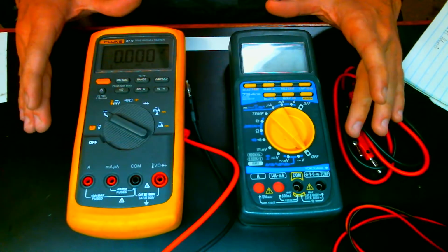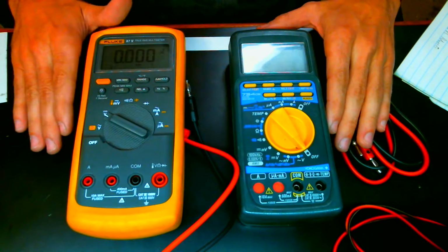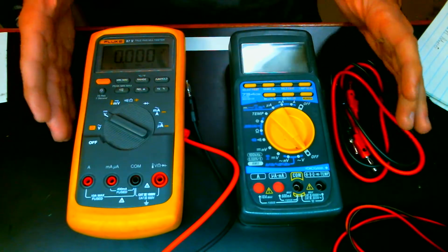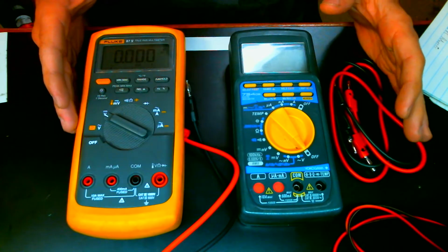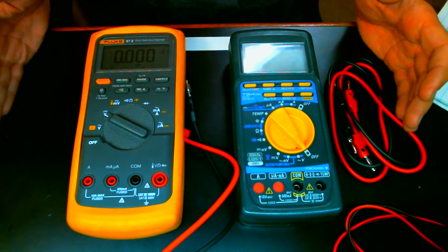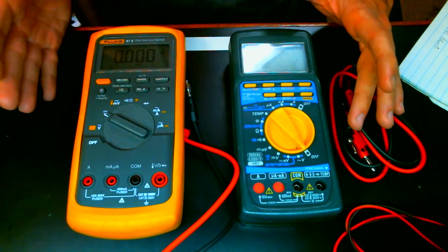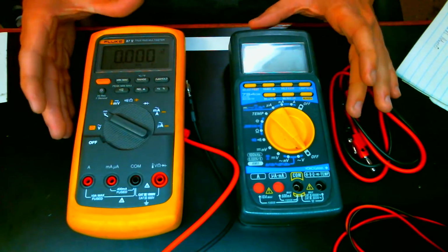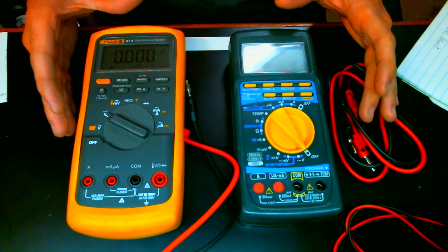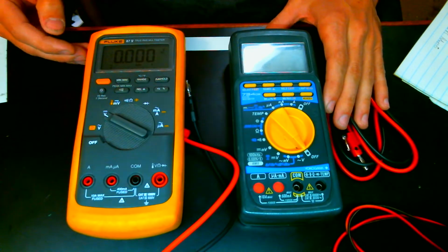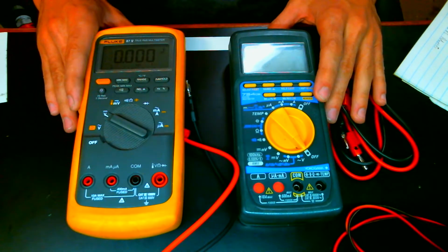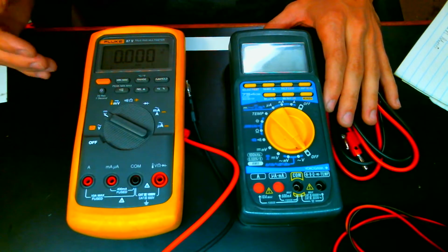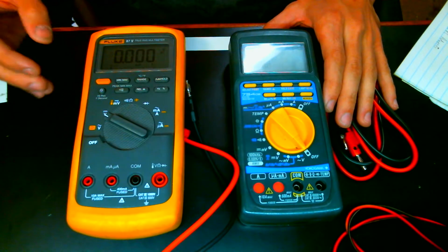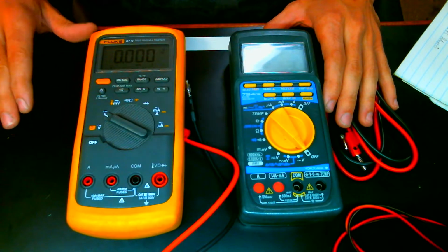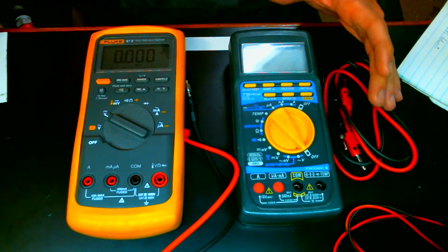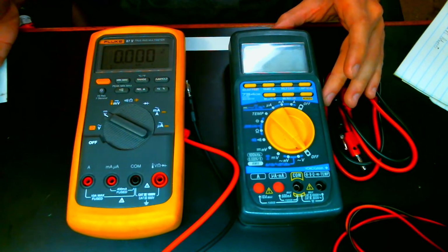because we're not trying to do any certification or calibration, which brings up another good point, that there's basically three tiers of what could fall under the umbrella of calibration. There's function testing, which is what we're going to try to get to today. There's certification, verification, kind of, they fall into the same thing. And then there is the actual full-blown calibration.